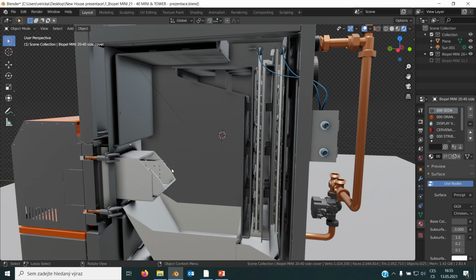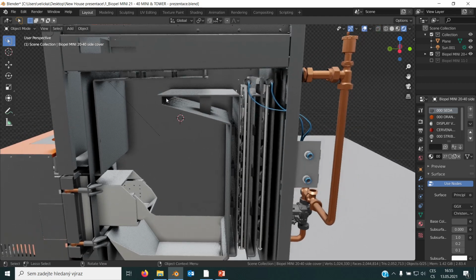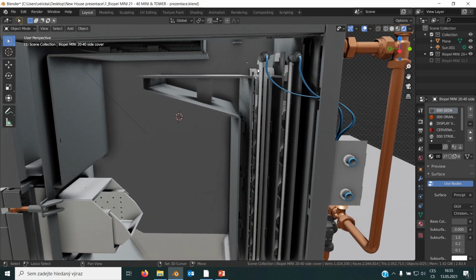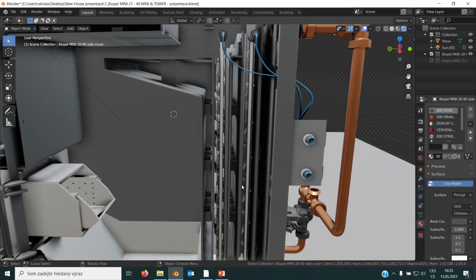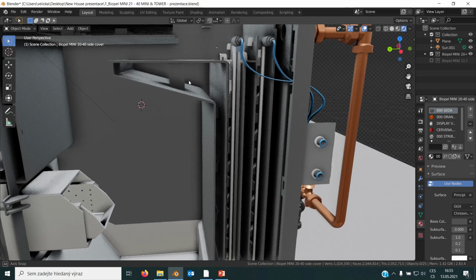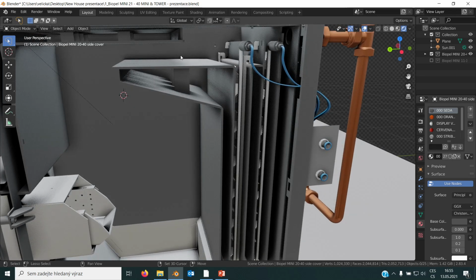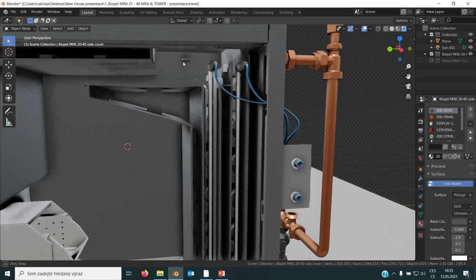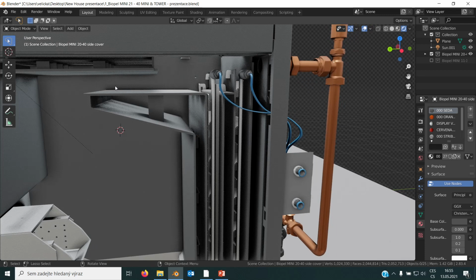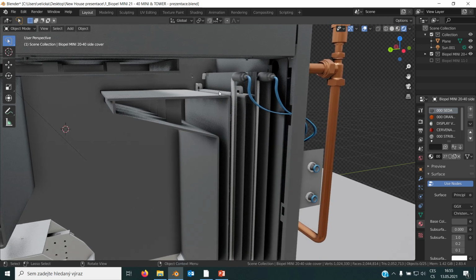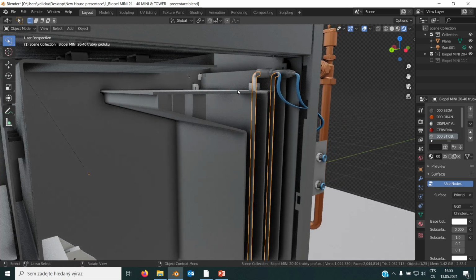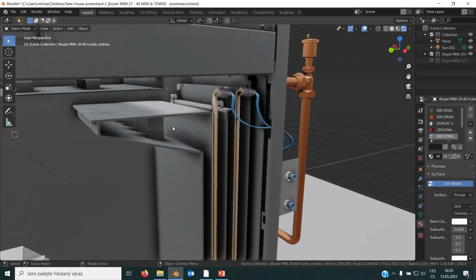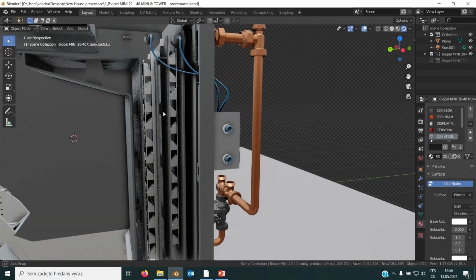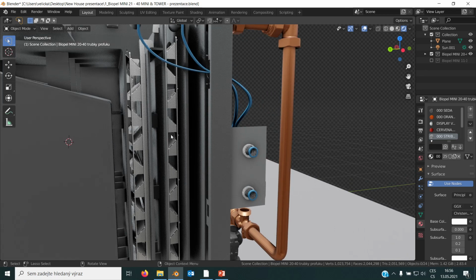The flame goes from the burner to the top here, and there is a horizontal space, and then it goes down, up, and to the chimney. This horizontal space can be cleaned manually from the cleaning doors from the top here. We have even a special cleaning tool which can quite easily move the ashes from this horizontal plate, but also the nozzles for the compressor cleaning clean this horizontal space. Okay, so it automatically cleans not only the horizontal space but also the space between each turbulator here.